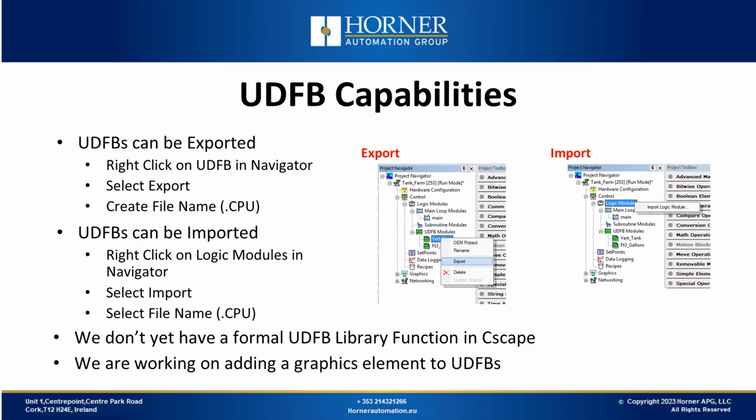Exporting and importing user-defined function blocks is handy for building a library across projects. To export a coded and tested UDFB, right-click on the function block in the navigator, select Export, name the file, and store it. Later, in another project or for sharing, import it by right-clicking in the Logic Modules section, selecting Import, and retrieving this file.